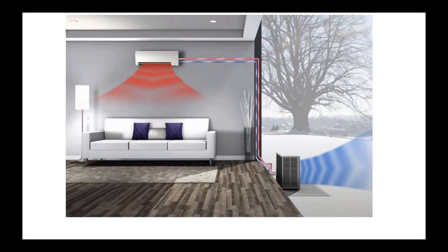Now you'll notice that there are two lines in this image, one red and one blue, depicting the flow of heat energy to and from the indoor and outdoor units. And those are copper line sets, so small coppers. Oftentimes, one line is 3/8 inches and the other one is 1/4 inch, and they're insulated. And along the same route with those copper lines goes a set of wires to provide power from the outdoor unit to the indoor unit, and also to communicate between the two so that the indoor unit can ramp up and down its fan to match the output of the compressor and to coordinate their operations based on the algorithms that are programmed into the system.